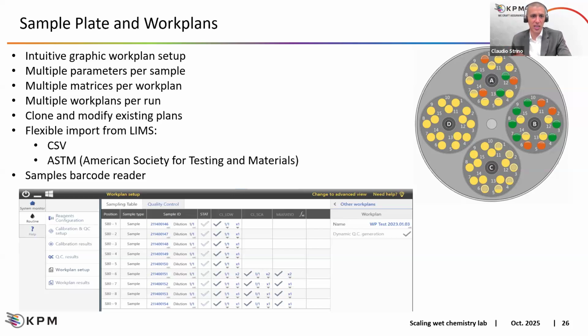We can set the import in two different ways. The standard way, that is with CSV, so the LIMS will generate the file we can import into the working routine, and also with the ASTM protocol, the American Society for Testing and Materials, which means a query mode. What does it mean? For each sample, we can send a query to the LIMS asking what are the parameters we need to run for this specific sample.